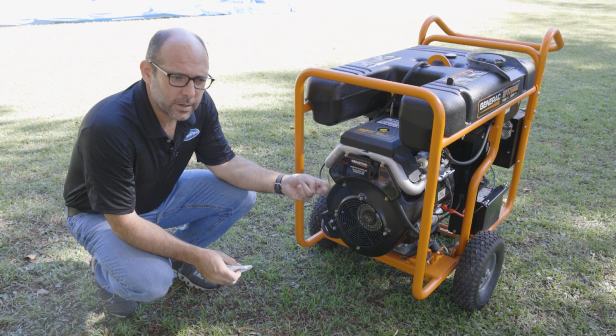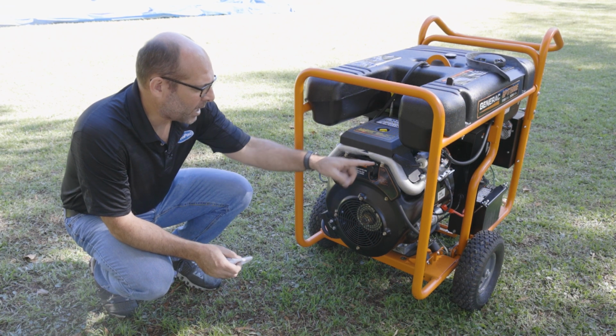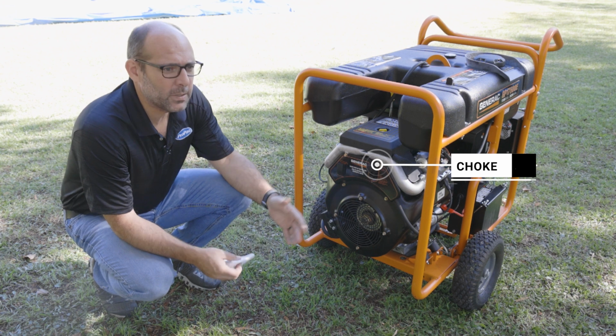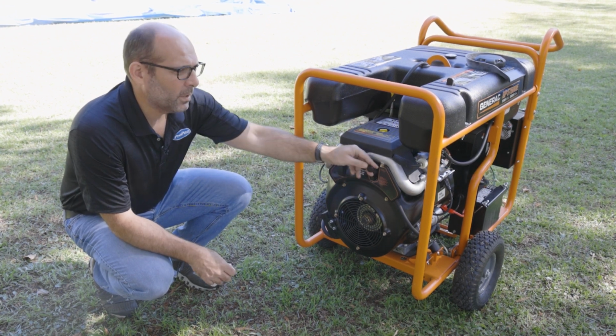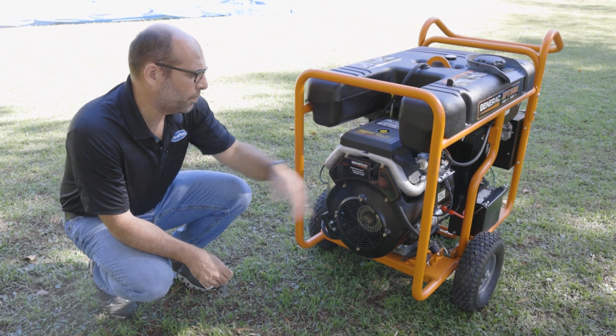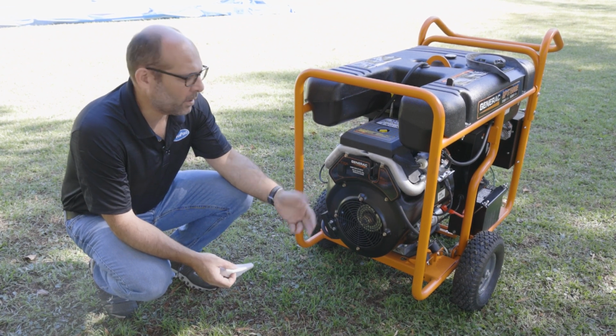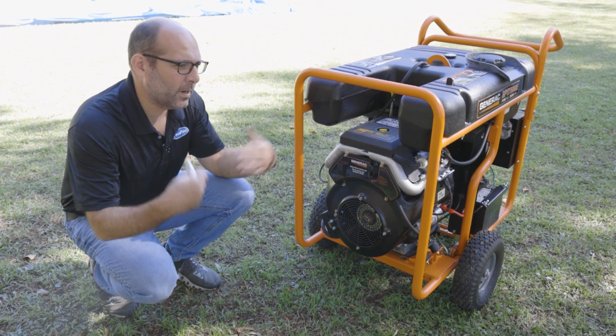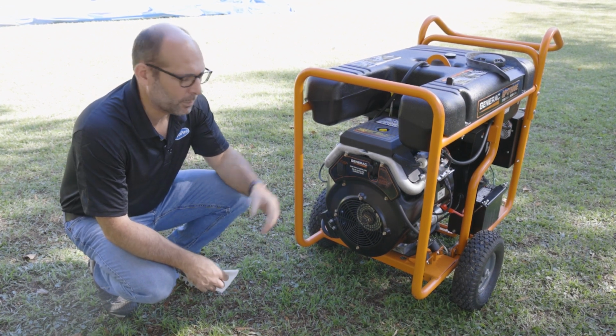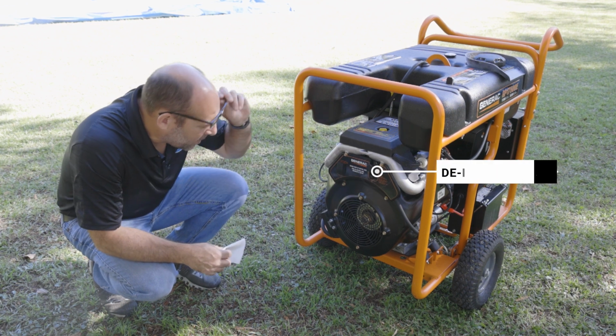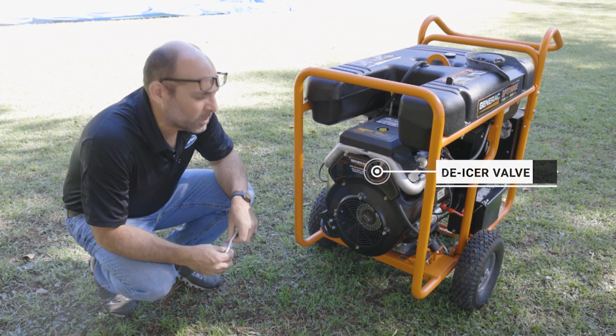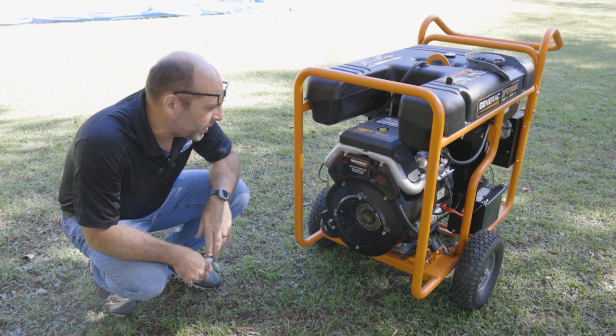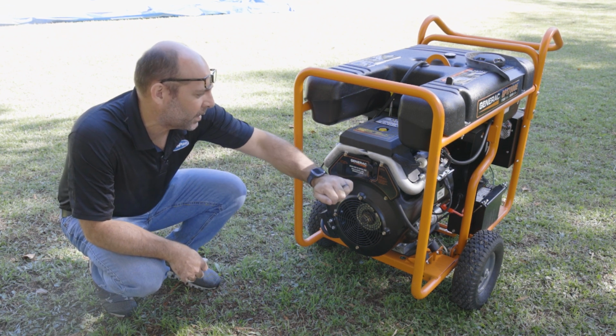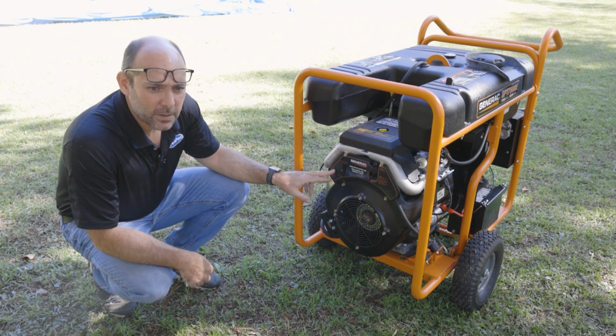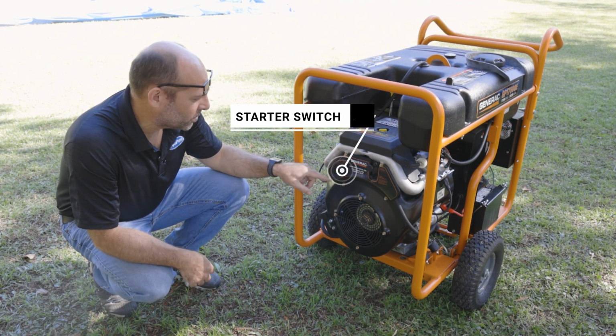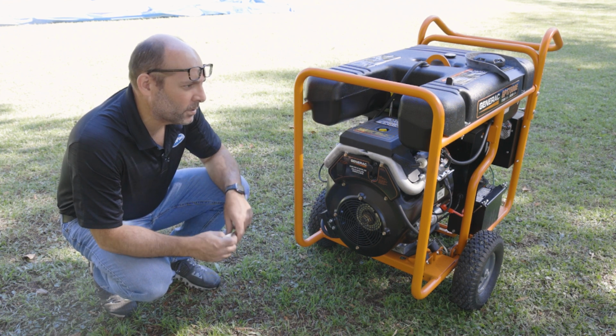All right, on this side of the generator, you got a couple different switches to activate. The top switch here is the choke. If the generator has not been started for a very long time, it's cold outside, you got a cold generator, you're going to pull that out for the first couple of times you fire it off. Otherwise, once the generator comes up, you can push the choke in and you'll hear it come up to RPM. The bottom is a de-icer valve. On the de-icer valve, for winter temperatures below 40, you're going to want to pull this out. So you pull that out. If it's above 40 degrees Fahrenheit, you can push that in. This right here is the starter switch. You're going to want to push to engage the starter switch and just hold it until the generator fires off.